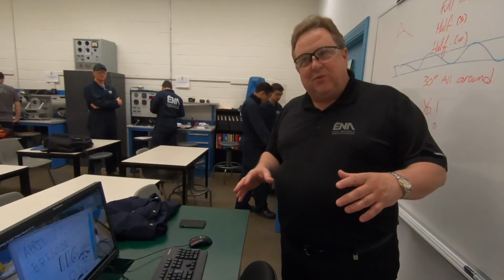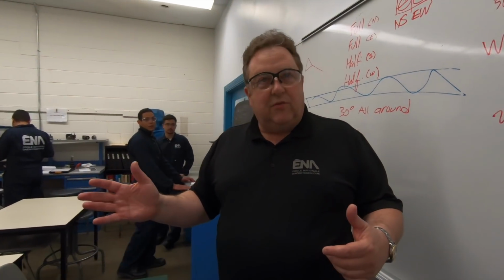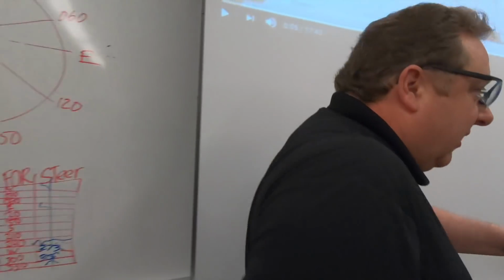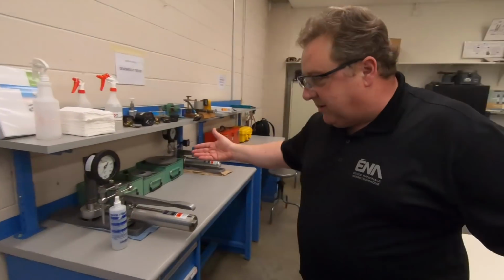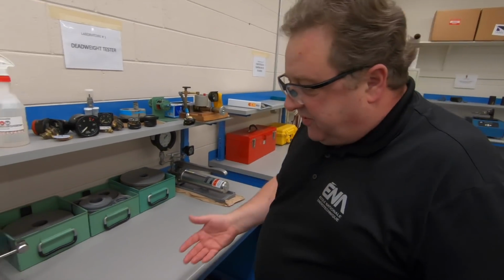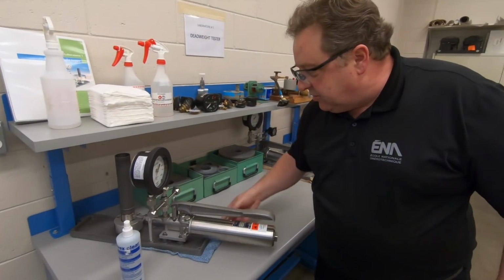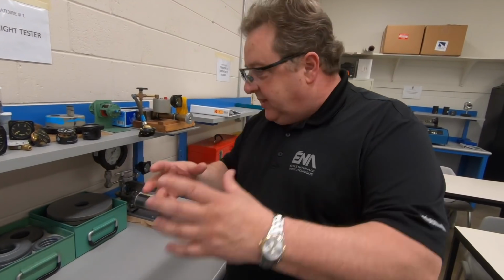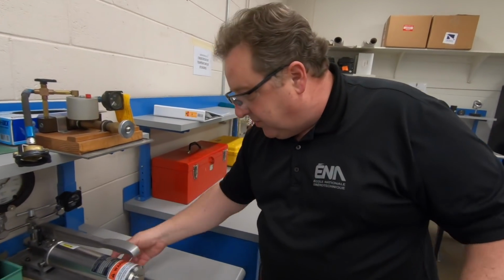As I understand, the purpose is to give you a quick rundown of what's going on. You'll see it's going to be lightning fast. First of all, we have 8 labs here. The first one is about calibration. A lot of people say, when we have torque wrenches and everything, we have to make sure it's calibrated. Well, this is how we calibrate the calibrators. These are very special dials that use gravity and very precise weight to generate pressure, and then we verify the testing equipment.